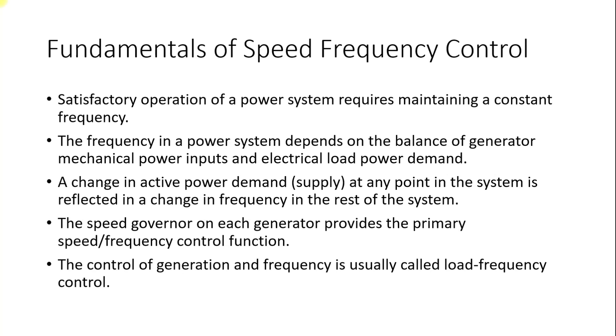A change in active power demand at any point in the system is reflected as a change in frequency throughout the rest of the system. The good thing about frequency is that it is a global parameter — the change in frequency is seen the same throughout the entire system. Whenever there is a difference between load and generation, there will be a change in frequency, and this change will be sensed by each and every generator in the system. The speed governor on each generator provides the primary speed-frequency control function. This control of generation and frequency is usually called load frequency control.